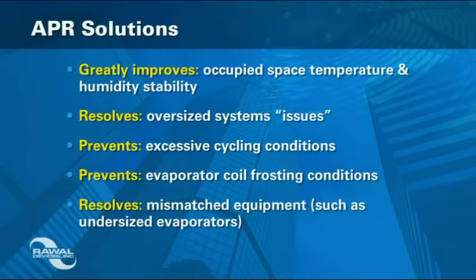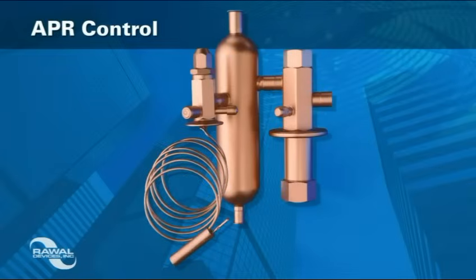As you have seen, the APR will enhance the control of DX air conditioning systems. It will extend their life expectancy two or more years by cutting cycling 30 to 60%. At partial load conditions, the electrical savings for the compressor can be as high as 12%. The APR Control has exceptional reliability.